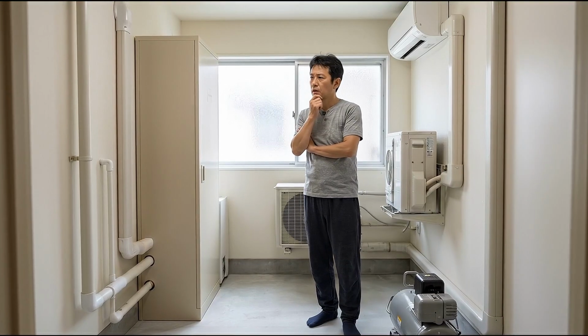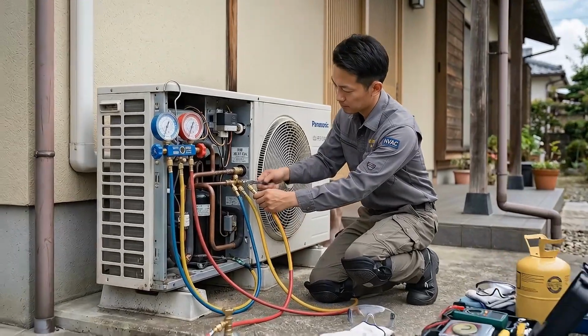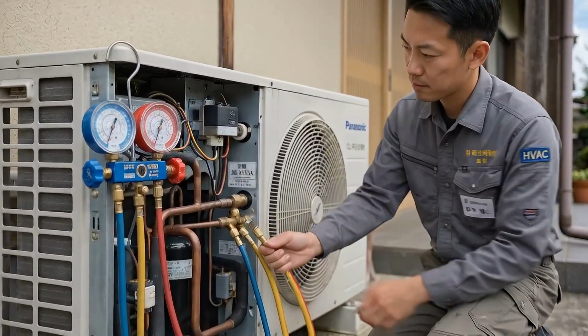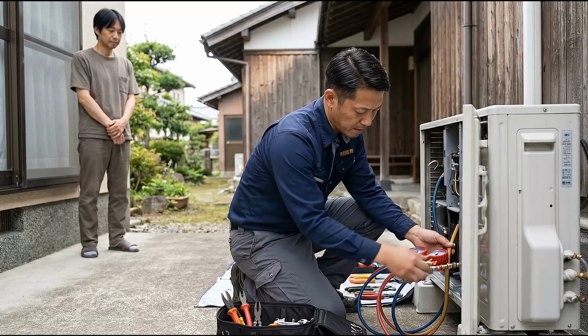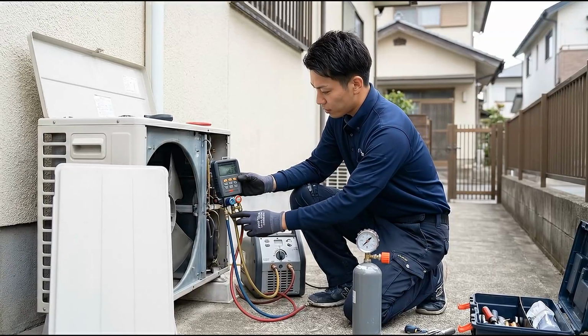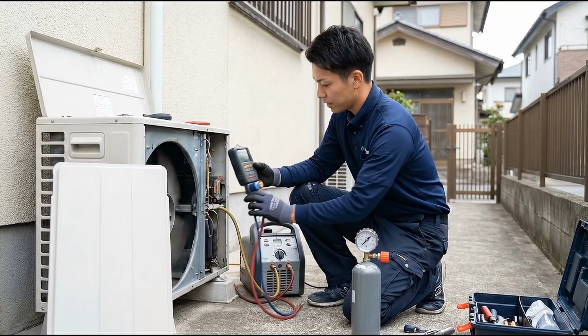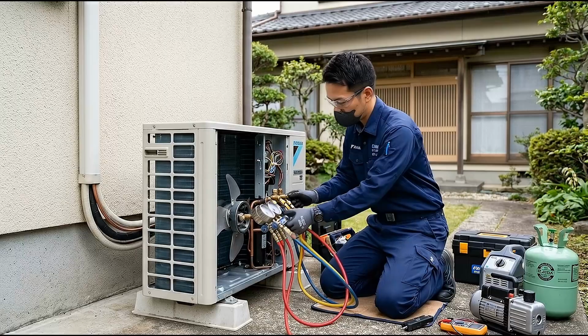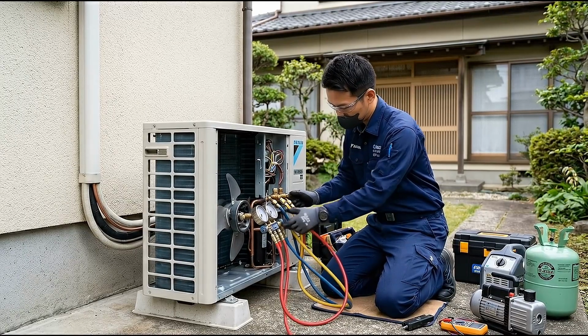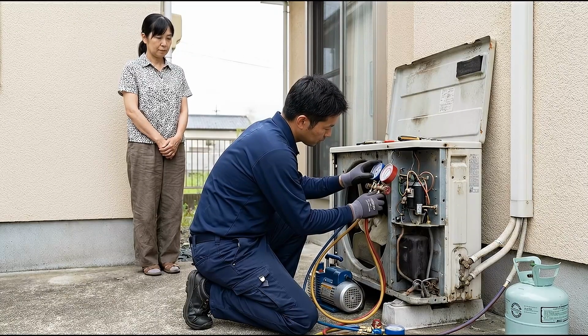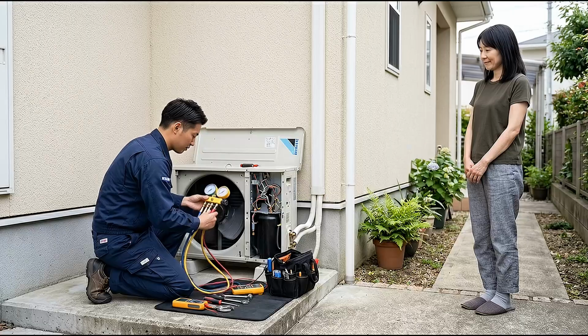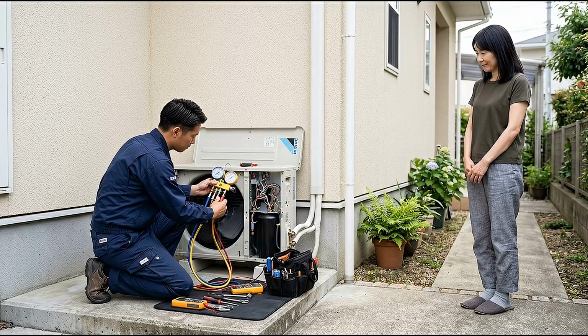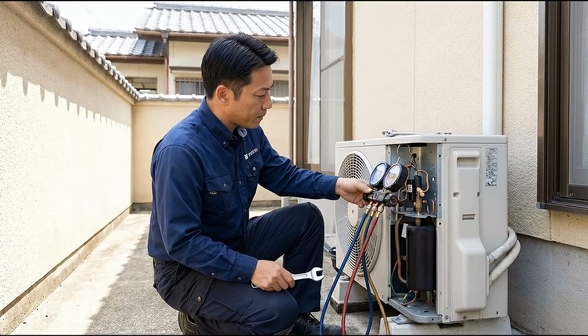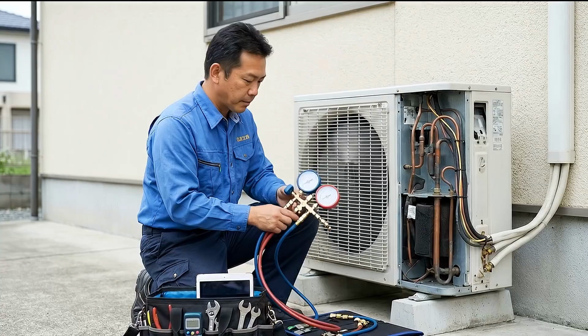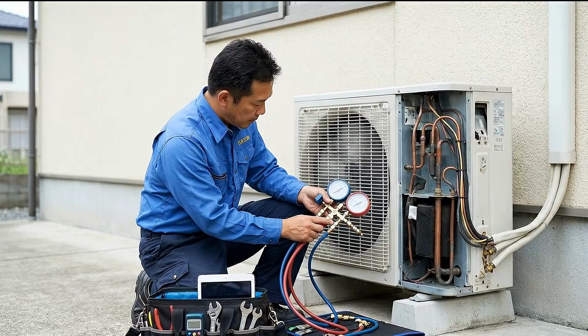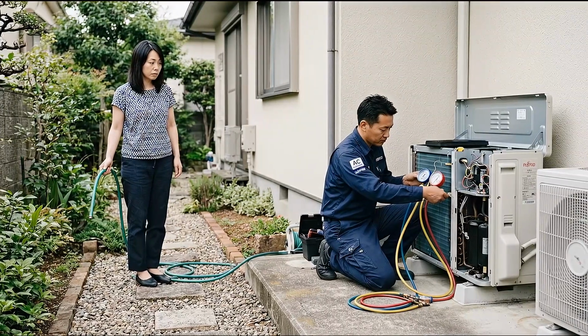But here is the other side. If the refrigerant charge is genuinely low, that means there is a leak somewhere in the sealed system, and leak detection and repair is skilled work. Refrigerant itself is a controlled substance handled under specific regulations. In Japan, the High Pressure Gas Safety Act requires licensed technicians for any work involving refrigerant, and DIY installation voids the unit's warranty and violates building codes. In the United States, the EPA regulates refrigerant handling under Section 608 of the Clean Air Act. Either way, this is not a garden hose job.